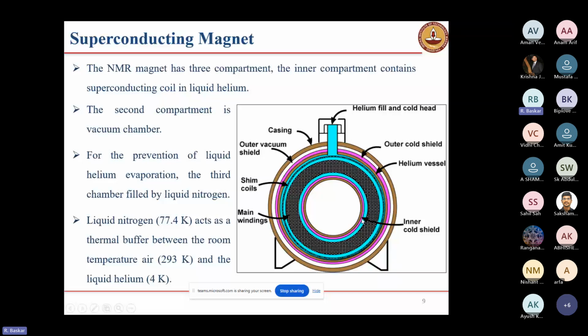This is the inner shield. After that, the next one is the shim, the RT, room temperature shim. Then this is the superconducting coil, and after that these are the outer shim coils, and this is the outer vacuum, and this is the casing, and this is the liquid helium fill-in port.